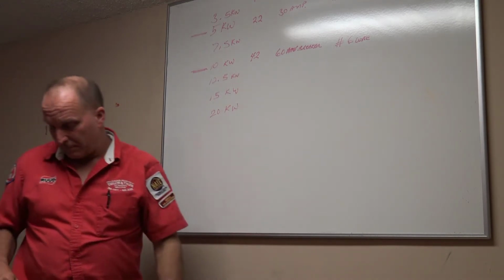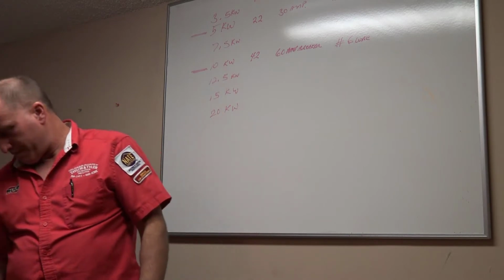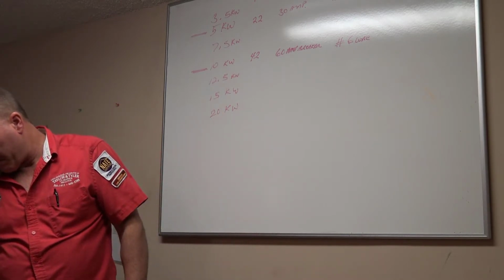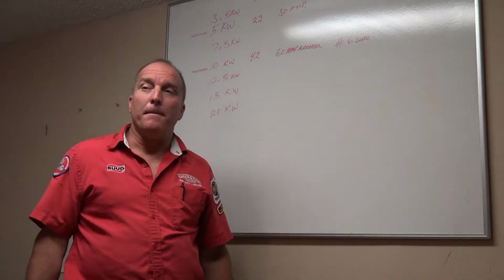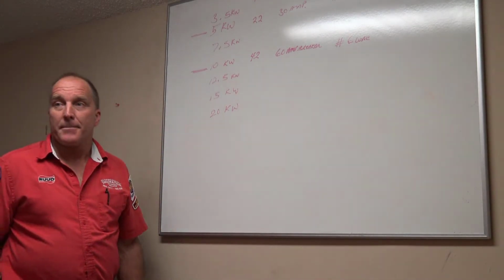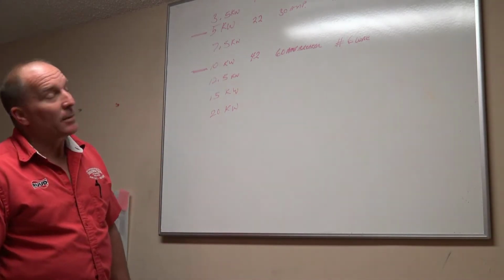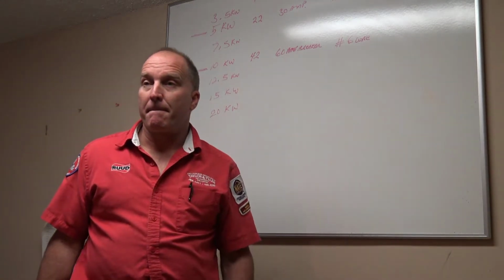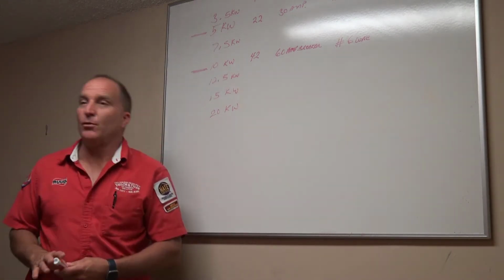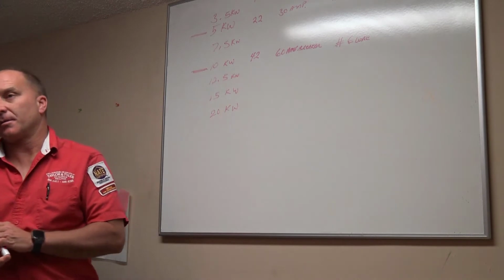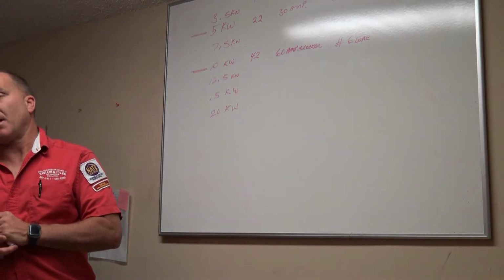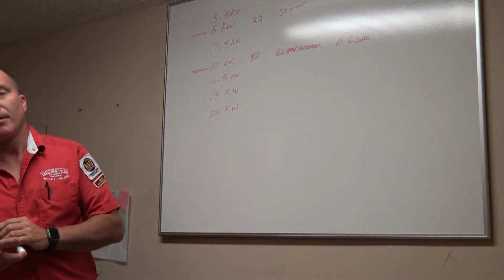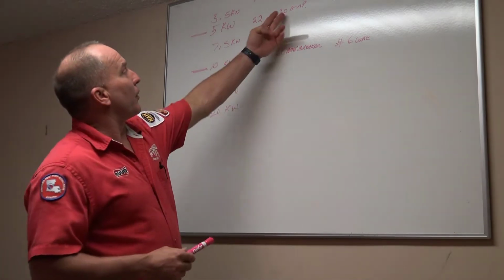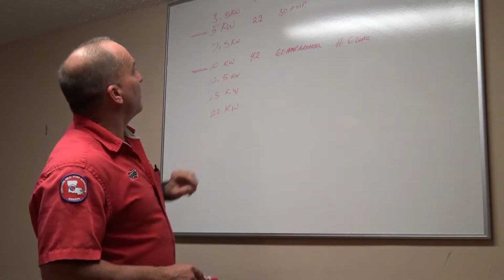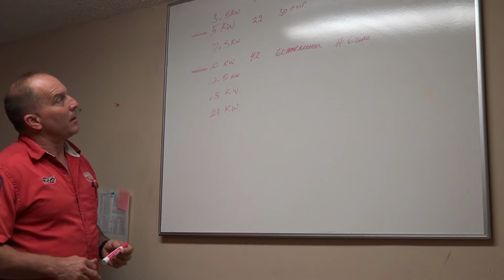You could run 2 number 10s on them. No. You can't run 2 number 10s, because you're going to have a 60 amp breaker. Oh, yeah, you're not going to have 2 30 amp breakers for a 10 kW heat system. You're going to have a 60 amp breaker. Okay, that's why. All right, so you've got a 30 amp breaker, number 10 wire. All right, so I'm good there.